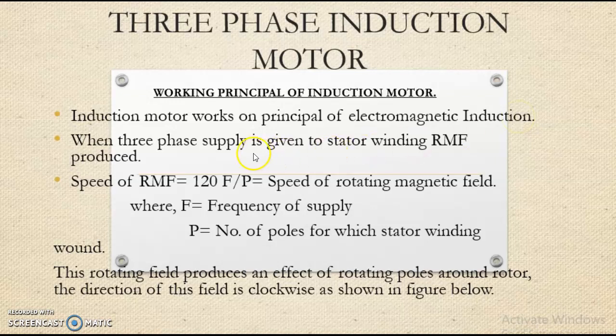When three-phase supply is given to the stator winding, a rotating magnetic field is produced. The speed of this rotating magnetic field RMF equals 120F/P, where F is the frequency of supply and P is the number of poles.